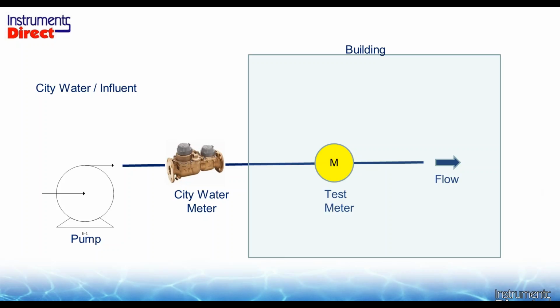And we get inside the building, and we now come down to limits of knowledge on how flow meters work. So here's a case. We walked into a hotel, perhaps, and we had an 8-inch city water line coming in, and they didn't believe the city water meter. They wanted us to evaluate it. So we come in the line. We put a flow meter on the pipe, an ultrasonic transit time flow meter. And the maintenance personnel said, okay, we're going to turn some water on. Watch your meter. We'll be back in a minute. And they come back in a minute, and we notice our flow meter doesn't blink a bit. They said, well, did you see that? We said, see what? They said, well, we flushed the toilet a couple of times on the 3rd floor. Did you see it? And the answer is no.